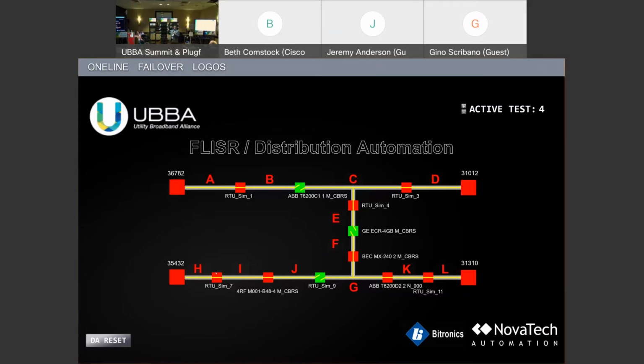Then we do our isolation function, figuring out where the fault is in the system, which is really a question of: did you see it? You work your way back. In this case, we work back from J to I. No, that recloser didn't see it, but H to I did. So we know the fault is in bus I somewhere.